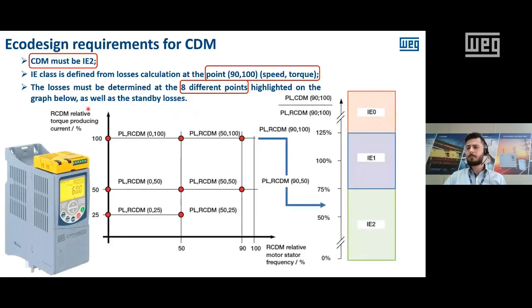So here, this graph is based on frequency, basically speed, and then the torque producing current. So we're going to have a speed torque graph. And the 8 points are here in this graph. So you have all 8 points, for which you should have the losses informed to the customer. And the IE class is determined by the 90-100 point, which is this one here.